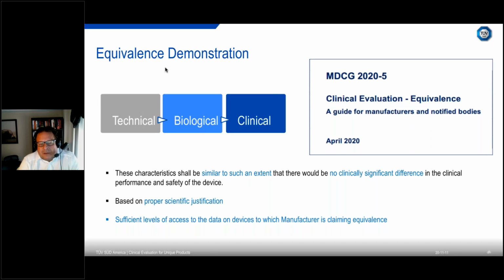The differences between your device and the proposed equivalent device can only be to such an extent that there would be no clinically significant difference. Of course, what does clinically significant difference mean? It depends on the device. For example, with hip prostheses, you can implant the femoral stem cemented or non-cemented. Those devices have different surface characteristics and a few design differences. Of course, it will never be possible to compare a cemented with a non-cemented hip prosthesis, as an example. If you have this kind of difference, it has to be based on a proper scientific justification, and on preclinical data.